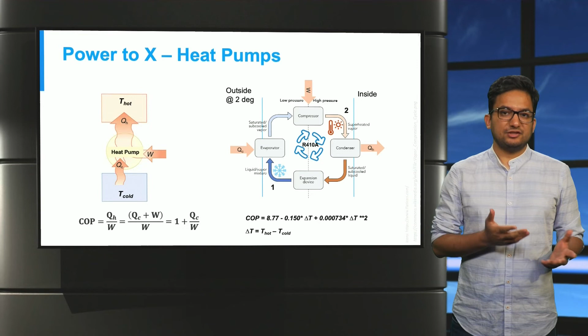Let me show you the impact of the detailed COP model versus the constant COP model in calculations for electrical power consumption. Consider the first day of January in San Francisco. The ambient air temperature for each hour of the day is shown in red, while the hot water requirement is constant at 55 degrees, shown in black. When we use this equation, the COP is calculated as shown by the red line in the figure, while a constant COP of 3, shown in black, is assumed, which is how heat pumps are usually modeled in energy system analysis.